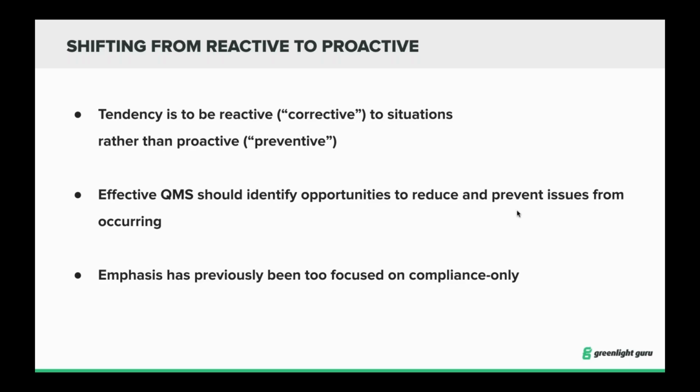There's a wealth of knowledge in a lot of different regulatory databases, like specifically the FDA MAUDE database, which has a lot of information. I can search by my particular product code or my indication for use, and I can see what other challenges others have already faced and use that as an input to my design and development process. So to me, the best way to be proactive at preventing issues with your product specifically comes into play when you're going through the design control practice and design and development processes.